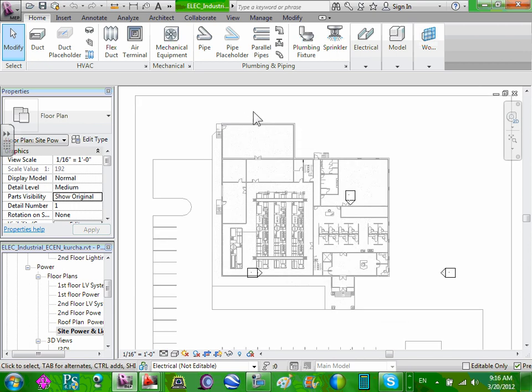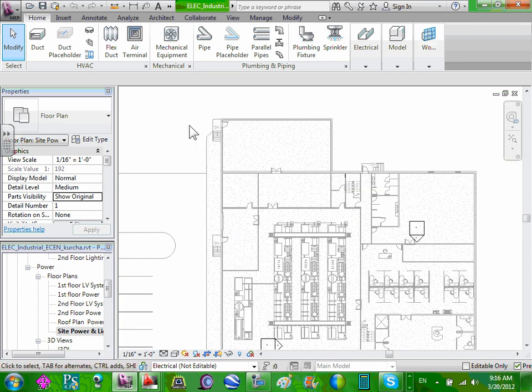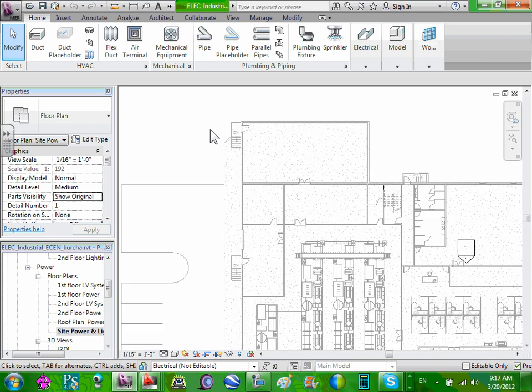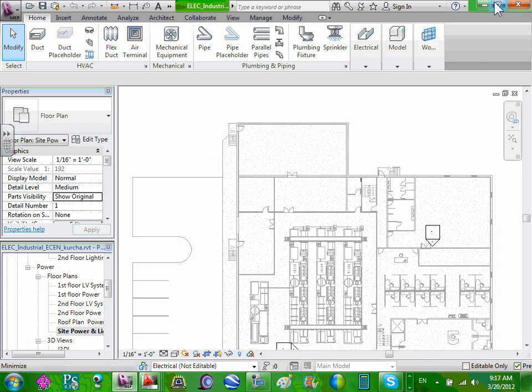So anyway, the electrical room back here, wherever you end up putting your main electrical service, the utility will need to have truck access to a pad mount transformer. So you're going to have a pad mount transformer outside where the utility will bring their medium voltage, 13,800 volt here in our territory. They'll bring that to the pad mount transformer. They furnish the pad mount transformer. You connect to it and bring the secondary service into our building and into our main switchboard, and we'll be bringing in 480/277 volt three-phase 4-wire power.